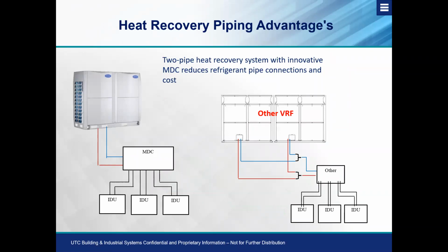And finally, I talked about the heat recovery systems having a single base rail and the advantages that offers over other manufacturers in the market. So we can see here, as we go to certain countries, other VRF manufacturers require a twin kit, which, if not done right, can starve oil back to the compressor. And you're also using more copper and more installation time. With our product, we have single point piping and single point electrical, which means we have one unit, only one source of main power, one source of communication, two pipes coming up. There are no twin kits. It saves on material and labor to install the equipment, and it also cuts down the complexity of having the twin kit that other VRF manufacturers need.